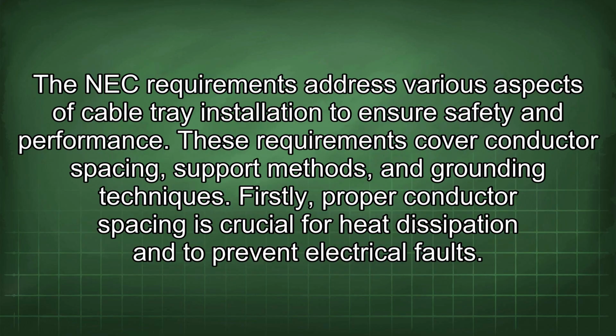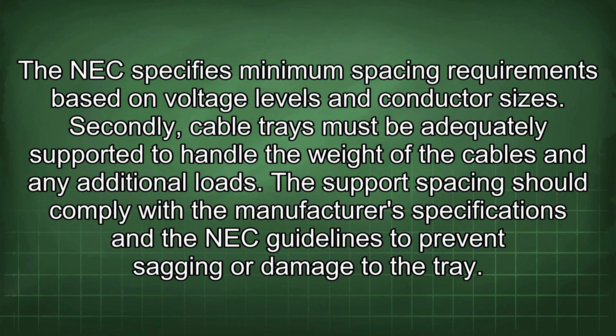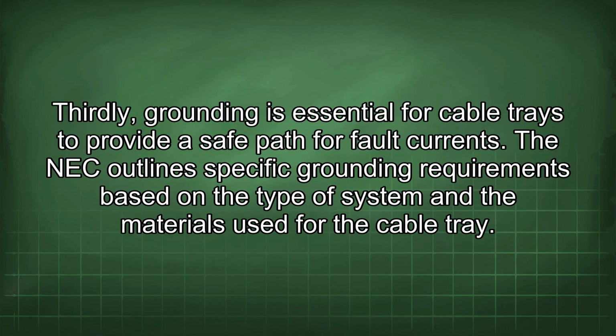proper heat dissipation. The NEC requirements address various aspects of cable tray installation to ensure safety and performance. These requirements cover conductor spacing, support methods, and grounding techniques. Firstly, proper conductor spacing is crucial for heat dissipation and to prevent electrical faults. The NEC specifies minimum spacing requirements based on voltage levels and conductor sizes. Secondly, cable trays must be adequately supported to handle the weight of the cables and any additional loads. The support spacing should comply with the manufacturer specifications and the NEC guidelines to prevent sagging or damage to the tray. Thirdly, grounding is essential for cable trays to provide a safe path for fault currents. The NEC outlines specific grounding requirements based on the type of system and the materials used for the cable tray.